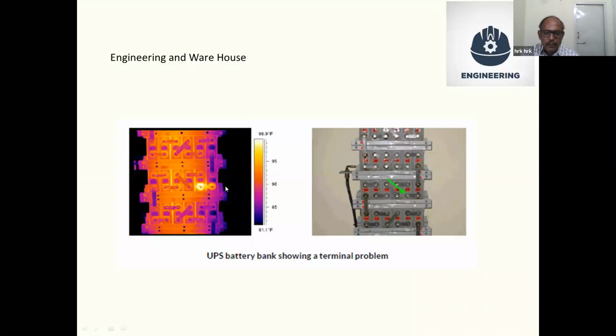This is another thing nowadays. There are a lot of accidents happening in UPS systems. One of the main reasons for UPS failure is battery failure. A loose temperature terminal or a battery internal reaction may lead to failure, and that we can find out. I will come to a future slide on how we prevented a UPS failure in a pharma company.